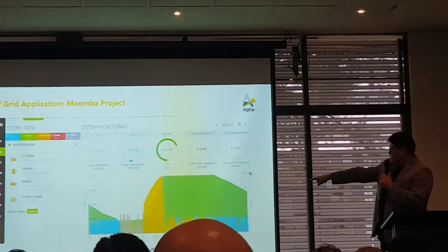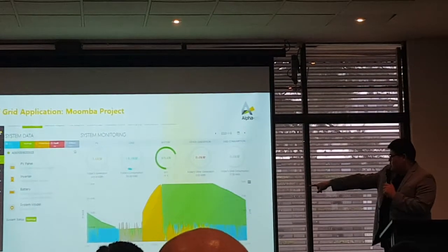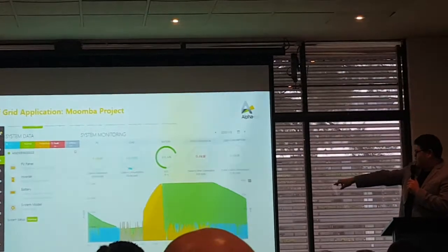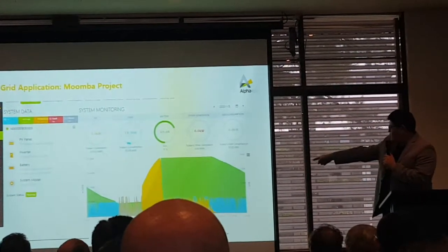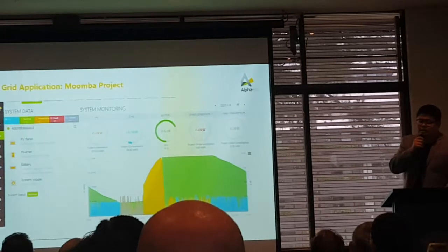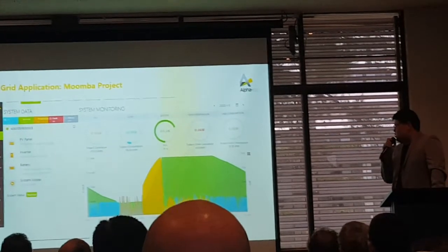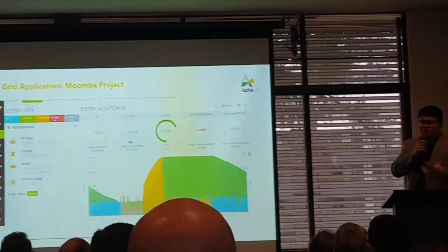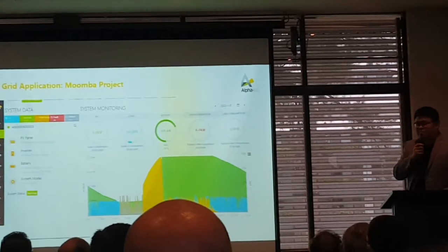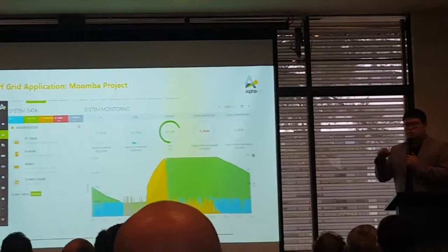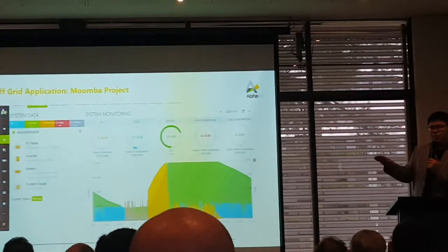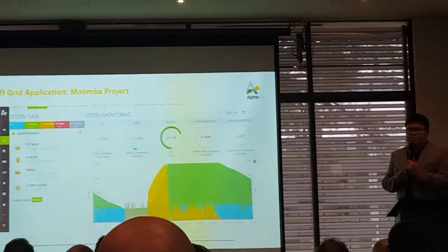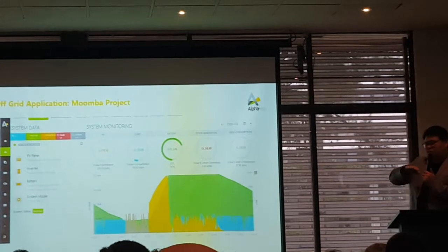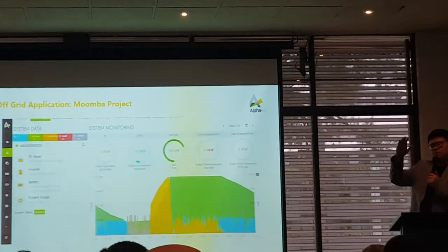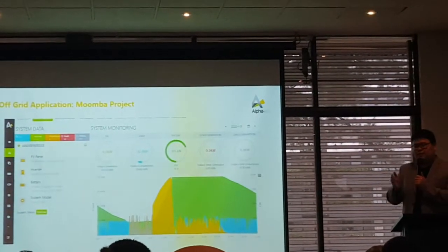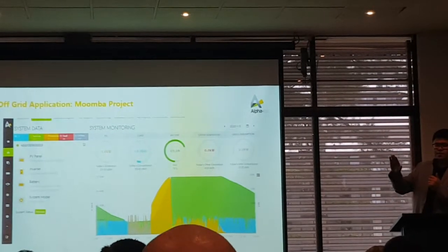During that dark browny, yellowy colored period, between 5 o'clock and 8 o'clock, that's when the diesel generator kicks in. So when the battery reaches, let's say 23%, which is settable, the system will talk to the generator and ask it to start working, charging the battery while also feeding the load. And when the battery reaches a certain state of charge, they'll tell the diesel generator to shut itself down and start the solar generation.